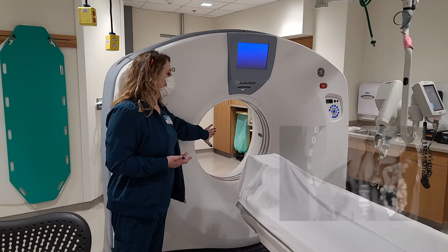So if you look into the inside here, it's circular, and there's an X-ray tube that is on one side of the circle, and then there's detectors that are on the other. So that tube's responsibility is to heat up and emit X-rays as a byproduct of that heat that are then projected across the patient as they go through the machine, and those detectors will catch that X-ray. And then it also spins the whole way around them. So the difference with a CAT scan image in the X-ray production versus a general X-ray is that you get a 360-degree view around the patient versus just a single flat image.